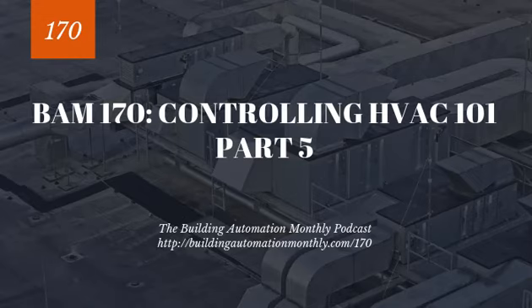All right, so at this point, we've talked about piping, pumping, DeltaT, overactive pumps. We've talked about pressure drop. We've talked about decouplers a lot, but we haven't really gone through them too much. So a decoupler is basically, instead of a mixing valve, you use this piece of pipe called a decoupler, and you use a variable volume secondary pump to modulate flow through the secondary. And what it is, it's a pipe segment, right?